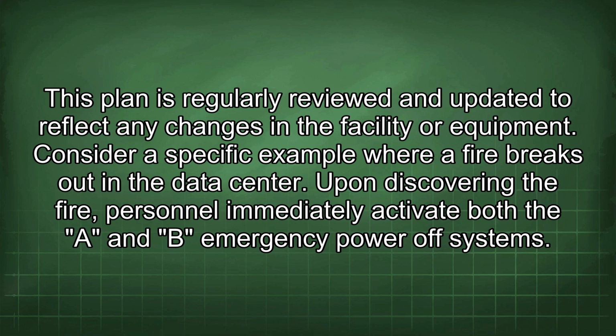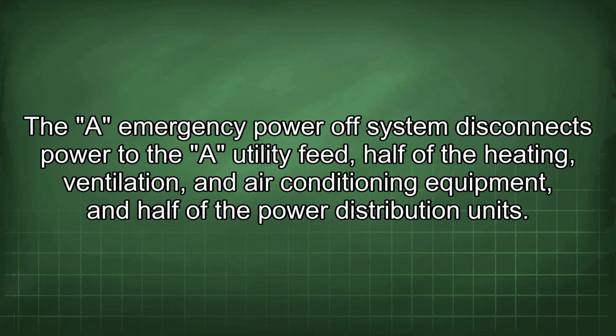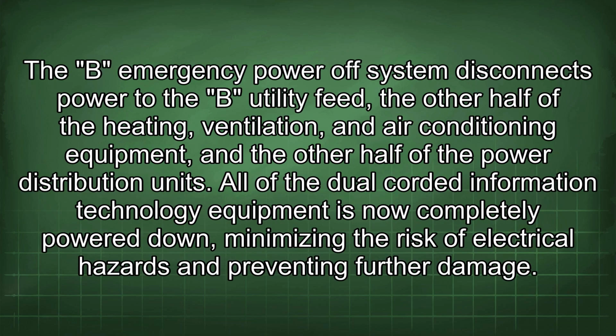Consider a specific example where a fire breaks out in the data center. Upon discovering the fire, personnel immediately activate both the A and B emergency power-off systems. The A emergency power-off system disconnects power to the A utility feed, half of the heating, ventilation, and air conditioning equipment, and half of the power distribution units. The B emergency power-off system disconnects power to the B utility feed, the other half of the heating, ventilation, and air conditioning equipment, and the other half of the power distribution units.